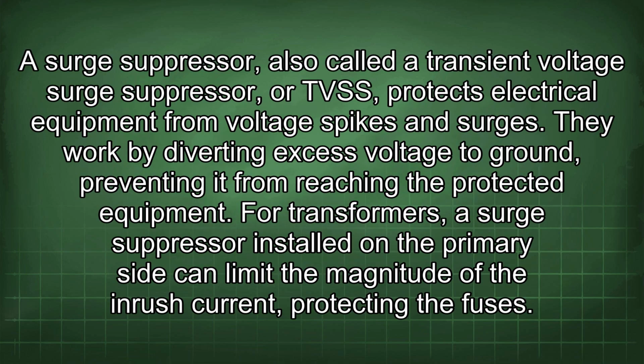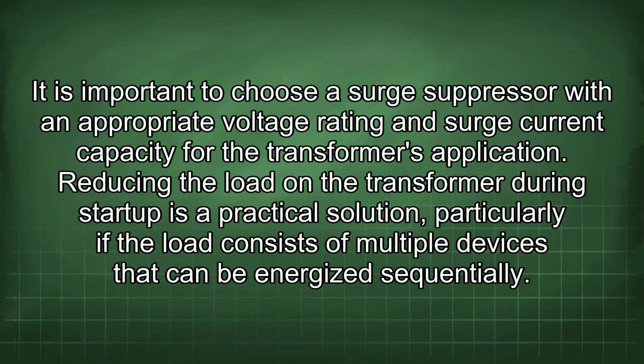A surge suppressor, also called a transient voltage surge suppressor, or TVSS, protects electrical equipment from voltage spikes and surges. They work by diverting excess voltage to ground, preventing it from reaching the protected equipment. For transformers, a surge suppressor installed on the primary side can limit the magnitude of the inrush current, protecting the fuses.